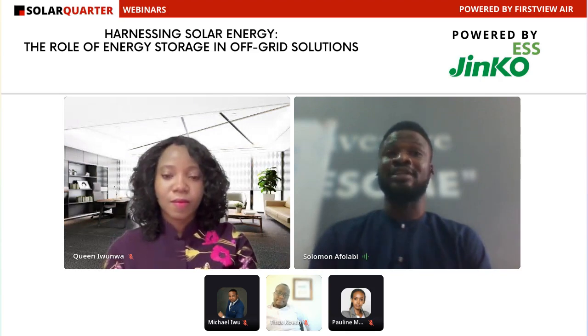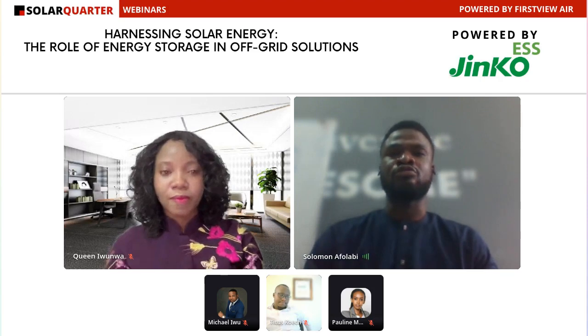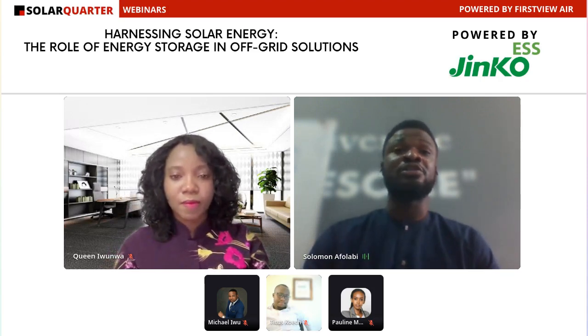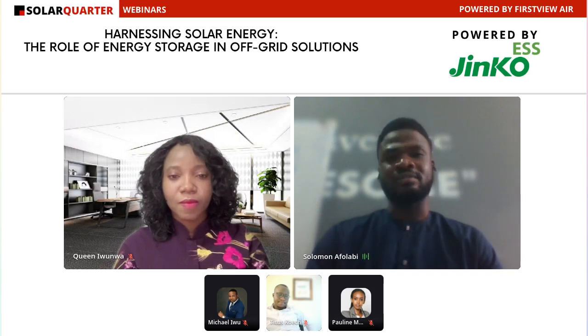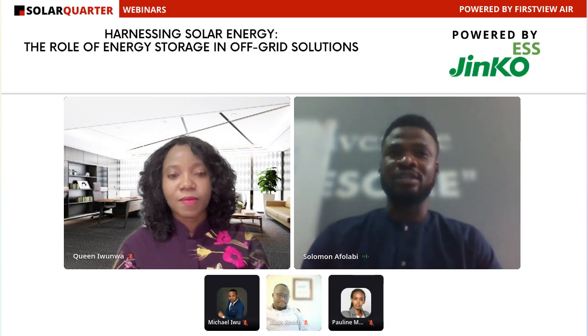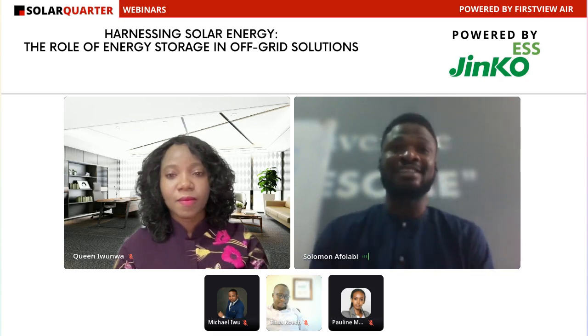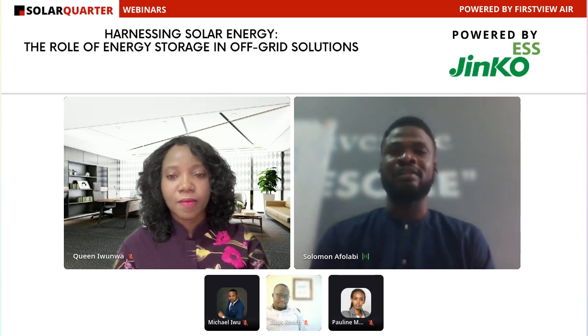Another key technical consideration when selecting an energy storage system is to make sure it has a battery management system and can easily be monitored remotely. Pauline mentioned some of these functionalities while presenting the Jinko ESS solution, and this is important because you don't want to sit in your battery cabinet for hours trying to check temperature by hand or hold a thermometer to the battery bank. Thanks to advances in technology, you can have solutions that let you remotely monitor temperature, operating voltage, operating current, and discharge rate. These are key pieces of information to keep in mind when working with your energy storage solutions.